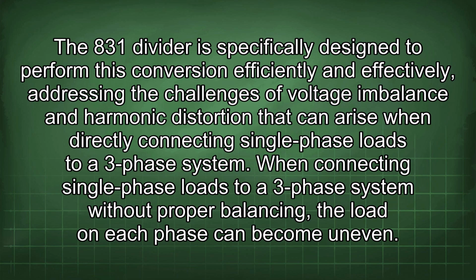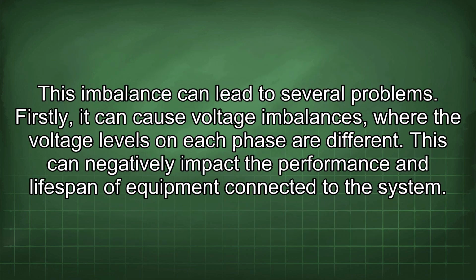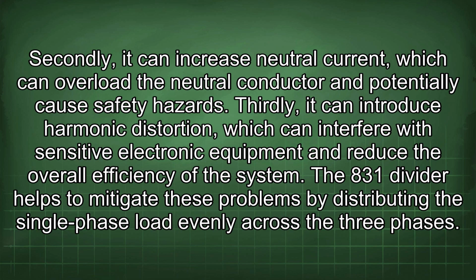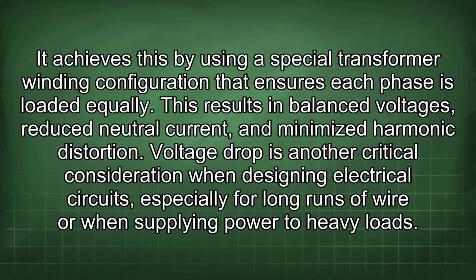When connecting single-phase loads to a three-phase system without proper balancing, the load on each phase can become uneven. This imbalance can lead to several problems. Firstly, it can cause voltage imbalances, where the voltage levels on each phase are different. This can negatively impact performance and lifespan of equipment connected to the system. Secondly, it can increase neutral current, which can overload the neutral conductor and potentially cause safety hazards. Thirdly, it can introduce harmonic distortion, which can interfere with sensitive electronic equipment and reduce the overall efficiency of the system. The 831 divider helps to mitigate these problems by distributing the single-phase load evenly across the three phases. It achieves this by using a special transformer winding configuration that ensures each phase is loaded equally. This results in balanced voltages, reduced neutral current, and minimized harmonic distortion.